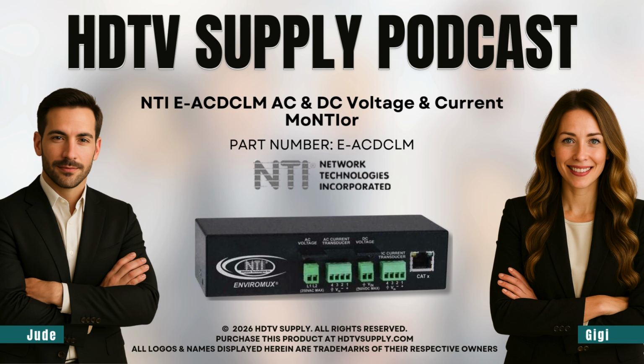And now on the DC side, it's working in a range of -60 to +60 VDC with a 1.2 VDC accuracy. But you mentioned the AC side has that 600 V isolation. The DC side is non-isolated. What's the engineering trade-off for that? It usually simplifies the design, and it can lower the cost for systems where the DC voltage is already within safe low voltage limits. Like telecom power or big battery backup? That's the perfect example. You gain simplicity because the risk profile is just lower than being right next to high voltage AC mains.